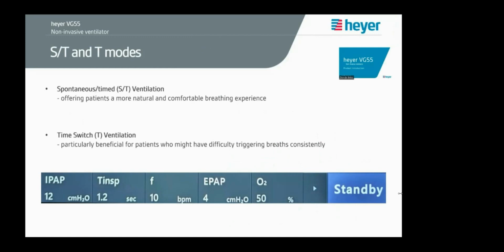Spontaneous timed ventilation mode, or ST mode, brings the advantage of maintaining a consistent gas delivery frequency as per the predetermined settings, promoting stability in the patient's breathing pattern. This mode not only ensures that the ventilator takes charge of pressure control and timing for mandatory breaths, but also provides assistance for spontaneous breaths, offering patients a more natural and comfortable breathing experience. With ST mode, the pressure aligns precisely with the preset IPAP value, optimizing respiratory support tailored to individual needs.